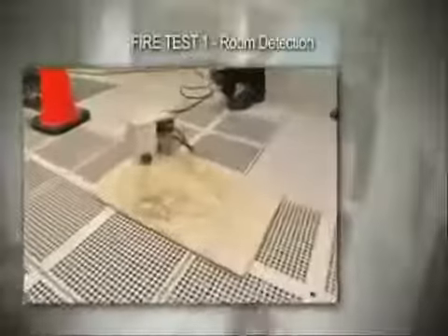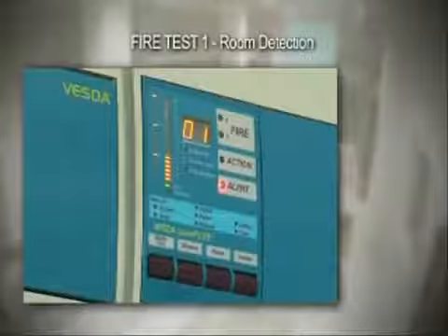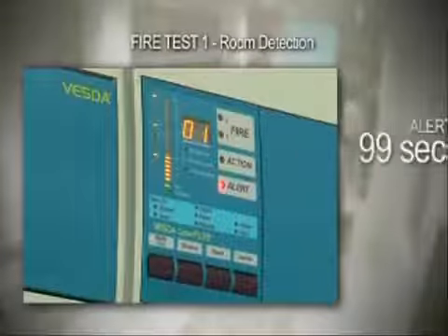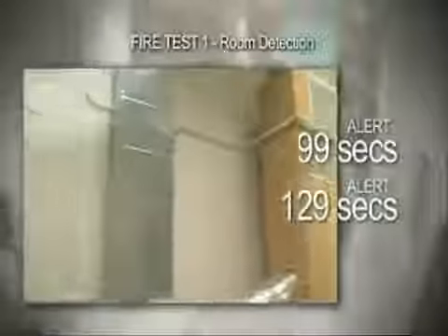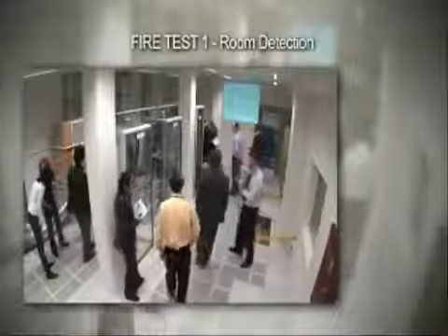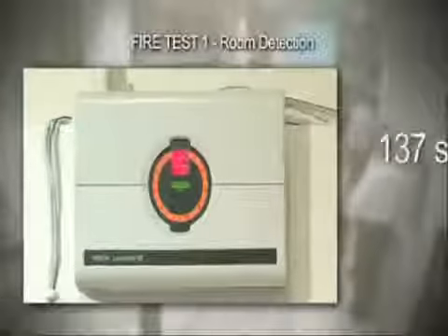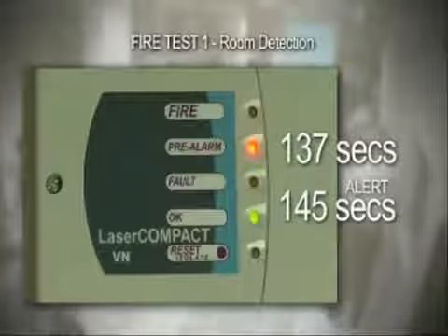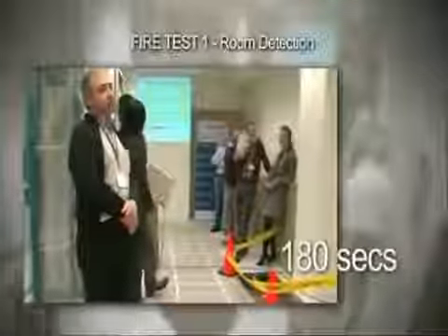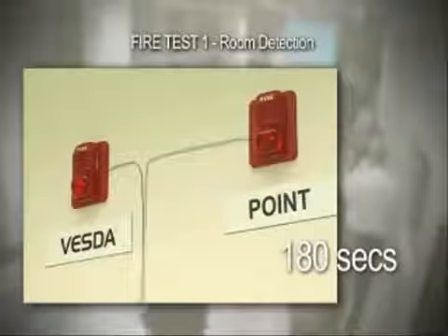Test 1 simulates an overheated PVC wire fire, which is lit on the floor at the furthest point of the room from the detectors. The VESDA Laser Plus detector on the ceiling goes into alert at 99 seconds. At 129 seconds, the VESDA Laser Compact detector across the return air grill goes into alert. The VESDA Laser Focus detector sampling in the cabinets goes into alarm at 137 seconds. At 145 seconds, the VESDA Laser Compact detector in the duct goes into alert. After 180 seconds, the point detector has still not detected the smoke.